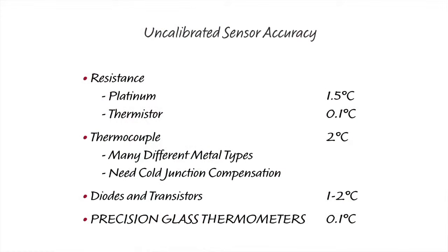For calibration purposes, if you need to calibrate some sensors, you can either buy an expensive system that's traceable to National Bureau of Standards. You can also buy some mercury and glass thermometers. These can be bought calibrated to better than 1/10 of a degree, and in a water bath or an oil bath, they provide a pretty good standard for calibrating other types of sensors.